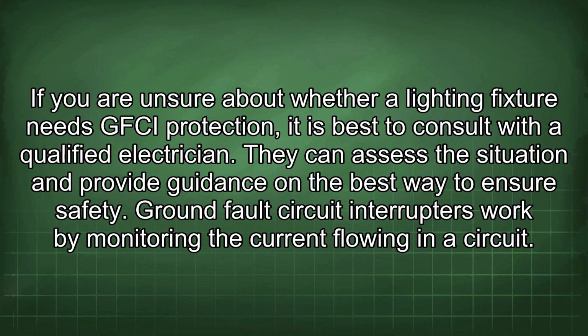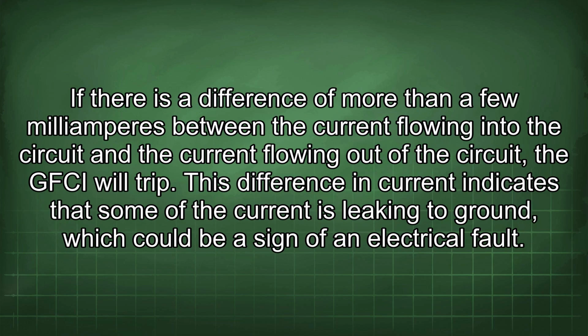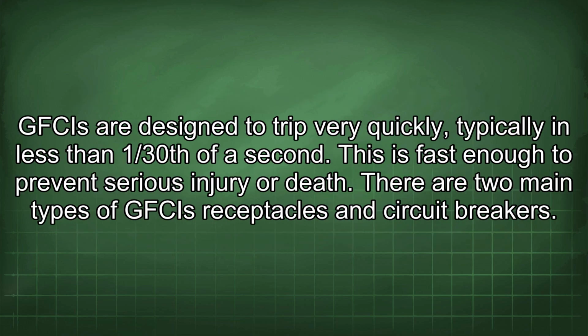Ground fault circuit interrupters work by monitoring the current flowing in a circuit. If there is a difference of more than a few milliamperes between the current flowing into the circuit and the current flowing out of the circuit, the GFCI will trip. This difference in current indicates that some of the current is leaking to ground, which could be a sign of an electrical fault. GFCIs are designed to trip very quickly, typically in less than 1/30th of a second. This is fast enough to prevent serious injury or death.